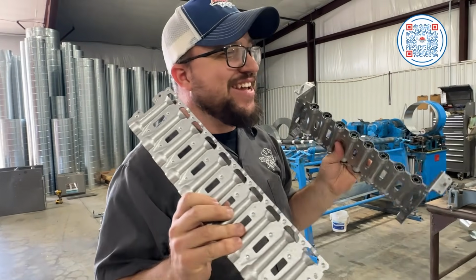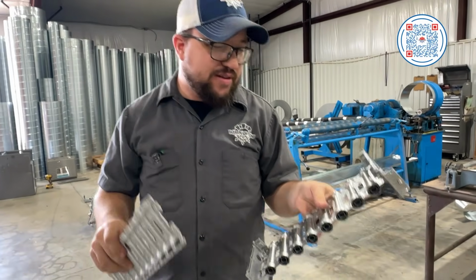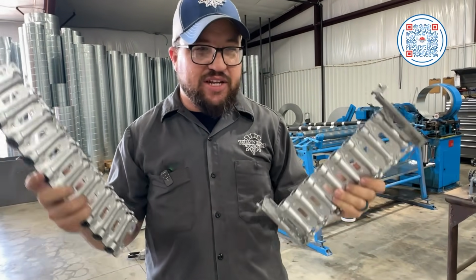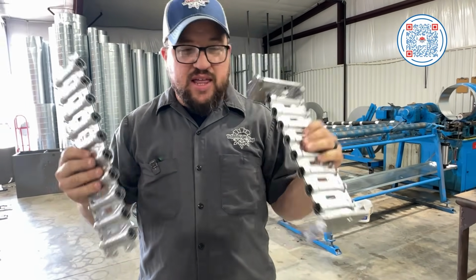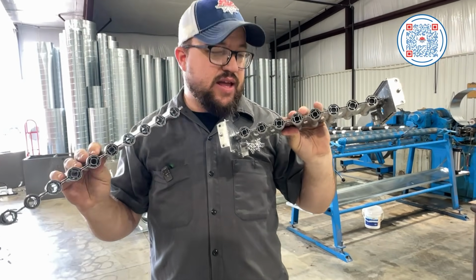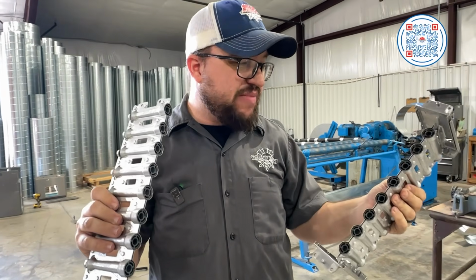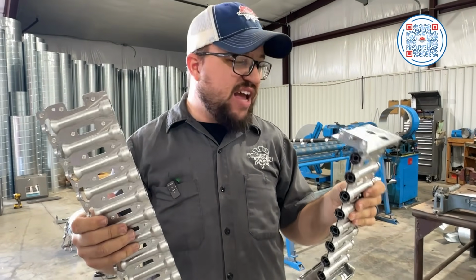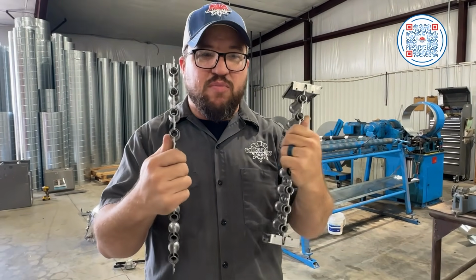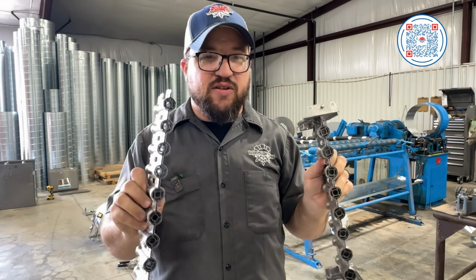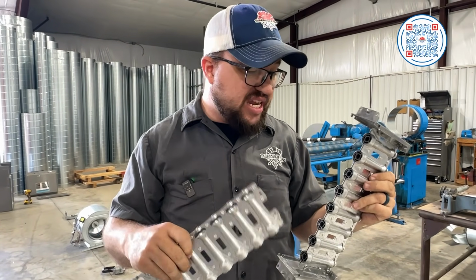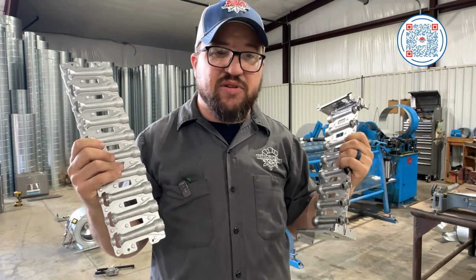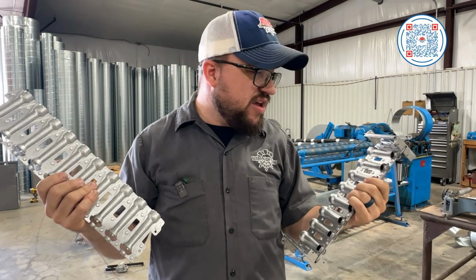So these are burners, and more importantly, burner assemblies, however you want to say it. Now, these can get dirty, and a lot of the problems we have with them is dirt. You don't really have too many problems with the actual burner assemblies. The dirt is going to be your biggest problem. So having them cleaned regularly is always going to be helpful and all that good stuff.